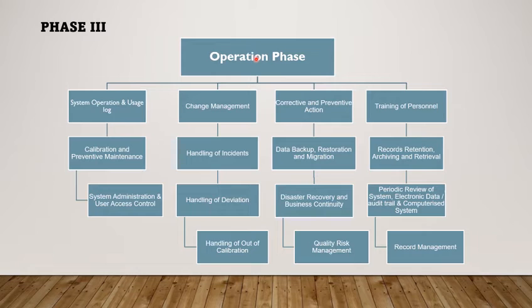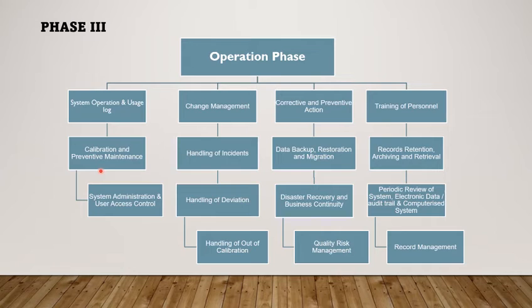Once the system has been validated and released for routine use, business continuity plans shall be available to ensure the validated state of the system is maintained throughout its operational life. Standard operating procedures to operate the relevant system and its usage log should be available. A change management procedure should be available whenever any modification is required with respect to the system, process or procedure. A procedure should also be available to take corrective and preventive action whenever any event is observed, to provide training to personnel, to perform calibration and preventive maintenance, to handle incidents observed during routine activity, and for backup, restoration and migration of electronic data generated by the system.